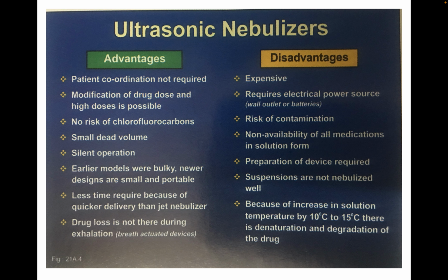Talking about ultrasonic nebulizers, the advantages are that patient coordination is not required, modification of the drug dose and high doses are possible, and there is no risk of chlorofluorocarbons, as is seen with MDIs. It needs a small dead volume, it is a silent operator, and earlier models were bulky, but the newer models are quite compact and small.